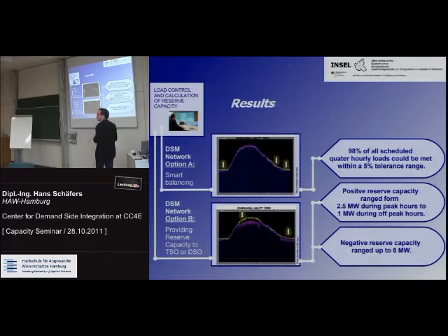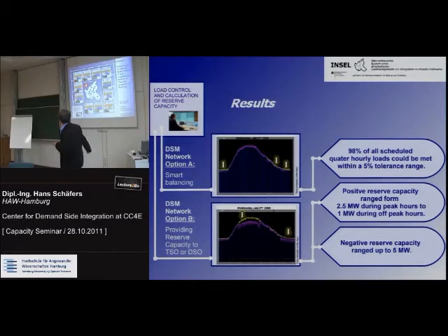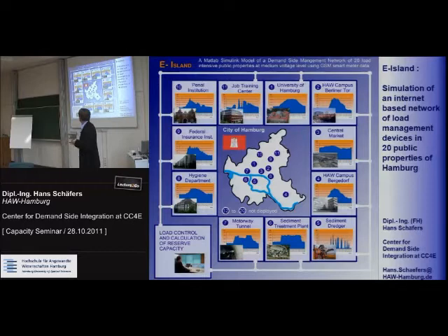And we asked the system, what can you take up? And we found it can take up quite a bit, 5 megawatts. But that's with a big but. And the but is we have one very large consumer here, the motorway tunnel under the Elbe, that has a lot of ventilation capacity. And that's emergency ventilation, right? When they have a fire, they need to suck out the smoke.